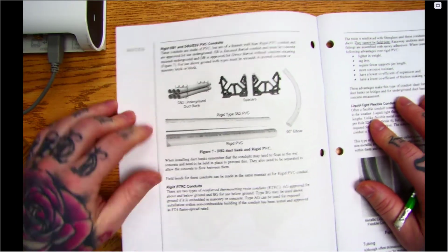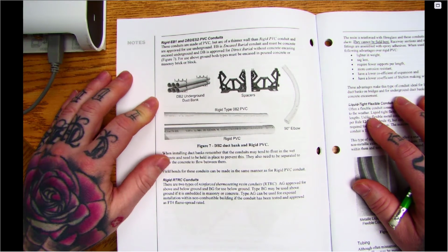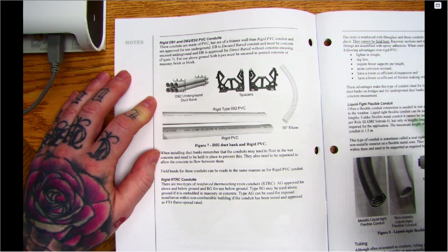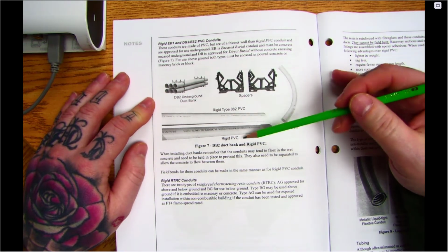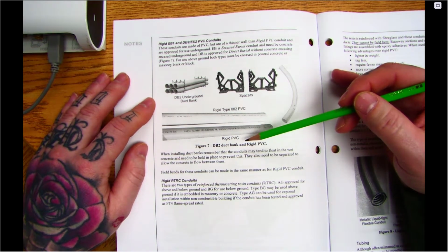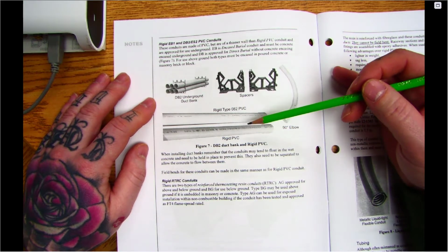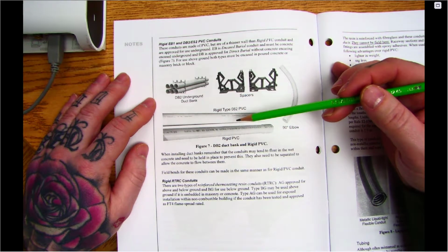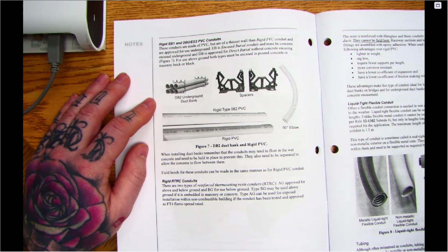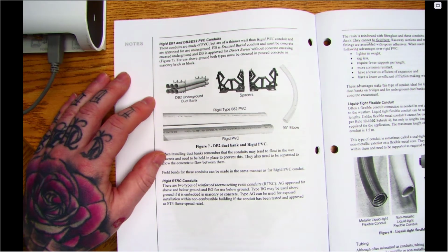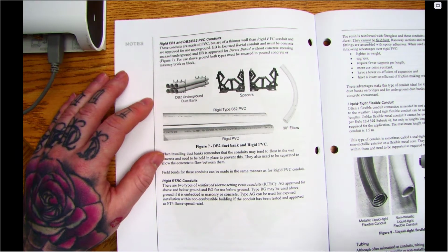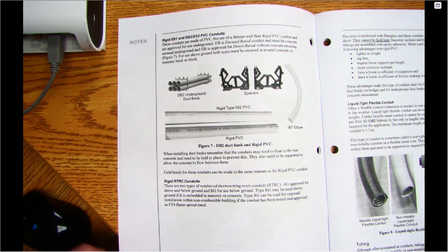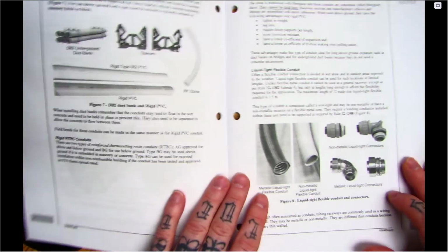And again, it talks about EB1 and DB2, different uses for that, okay, whether they have to be encased in concrete. Again, make sure you read the differences. The DB2 I've used before was all for undergrounds for a townhouse complex. So they ran all the underground feeds in DB2, and then we attached rigid PVC to that DB2, so when we came up out of the ground it was PVC, because you can't have DB2 running out in free air. So we do have certain stipulations and rules for using that. Okay, but again, read through it, not too crazy.